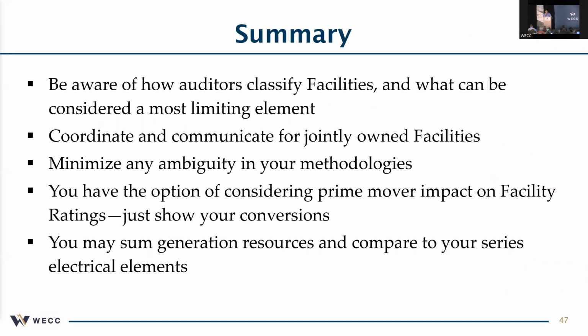So in summary, be aware of how auditors classify facilities. You can hopefully avoid any issues if you're just aware how we're looking at these things and what can be considered a most limiting element. I think there's too much emphasis on the most limiting element thing. You don't have to set your rating equal to the most limiting element. Most people do, but all you have to do is respect it. That's just one line in the R2 and R3. Just one of the considerations is don't exceed the most limiting element. But you have to identify that to make sure it doesn't happen.